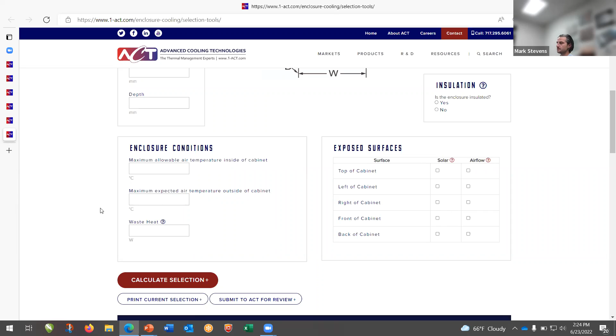All of this information is important because the natural losses off the cabinet tend to be pretty significant in most applications. If you don't account for those, you wind up oversizing the cooler for your system, which may not be an effective solution.